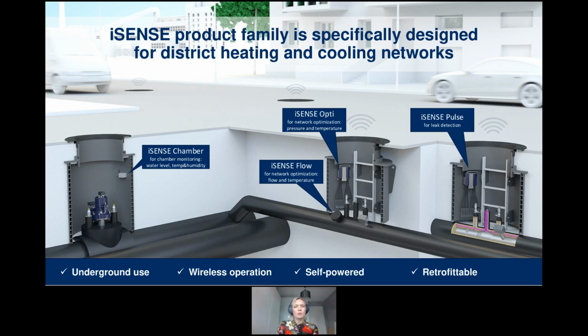Thirdly, our products are self-powered. Again, it's not possible in district heating networks that you would have electricity underground. So we produce electricity with a thermoelectric generator, which you can see in the right-hand corner. It produces electricity based on the temperature difference between the outside of the casing pipe and the hot pipe inside the insulation. And fourthly, the most important thing, all of the products are retrofittable, because we know district heating and cooling networks are growing slowly.